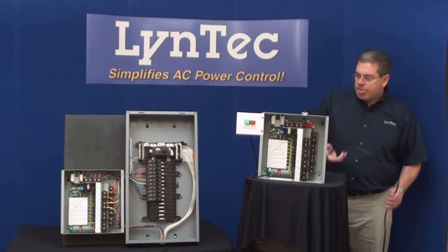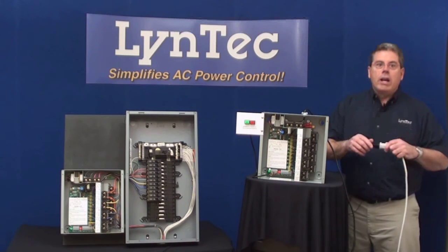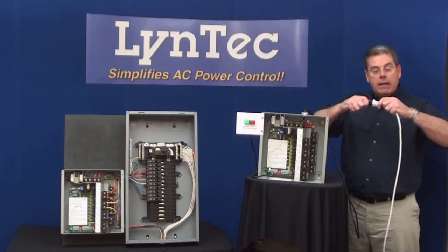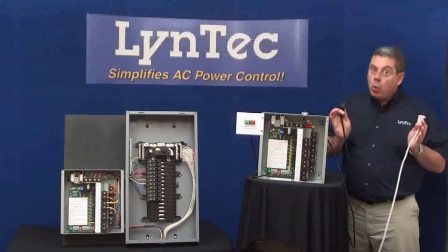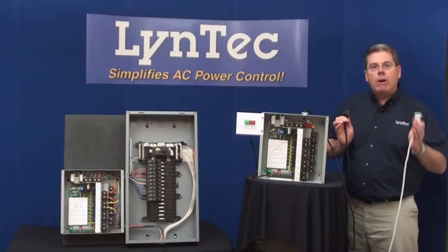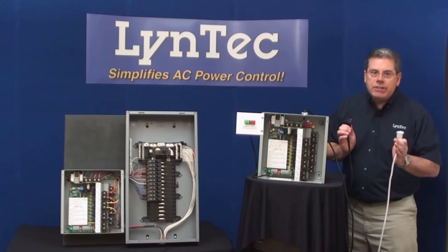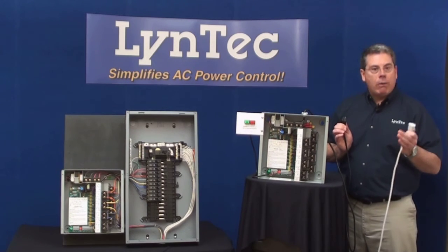Let me demonstrate. Since this is a demo unit, I'm powering it from this extension cord. Now when I unplug the cord, notice that the relay is powered down after the power has been cut for two seconds. LynTec makes sure that we always store enough electrical charge to power ourselves down in the absence of electricity. Now the reason we do this is so that we can always power back up as programmed once power is restored.